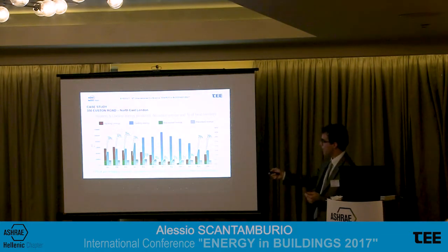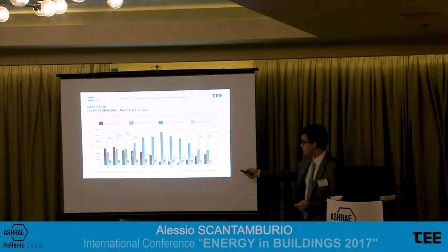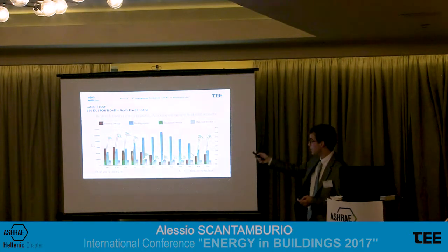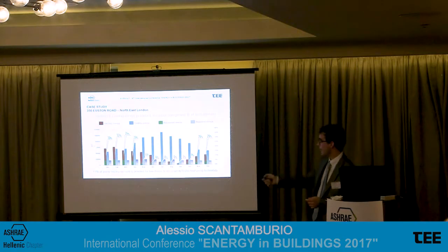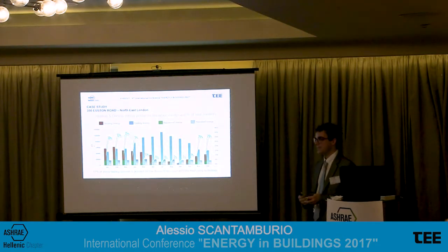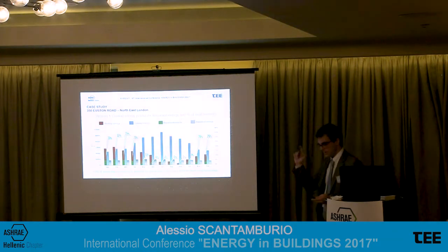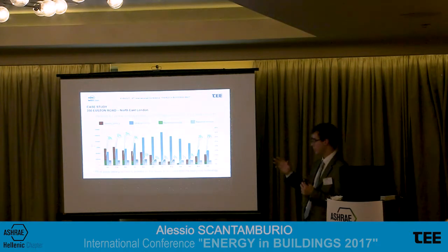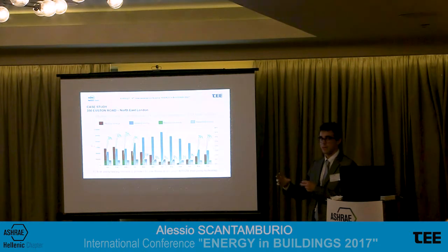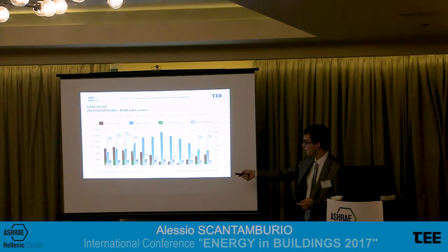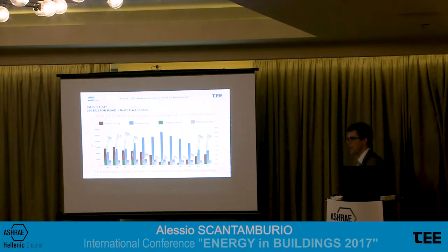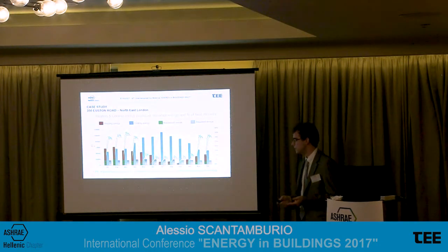So, as you can see, it is true that this plant is requiring heating and cooling for most part of the year. As you can see, the blue line and the red line are cooling and heating demand. The gray line is the power, the energy consumption of the unit, and the green line is the energy which is recovered, let's say, for free. In the previous slides, we saw that when the 4-pipe system is producing hot water and cold water at the same time, we can consider that one of these useful effects is for free. And this is the meaning of this green line. So, this is from the numbers in terms of power, cooling, heating, recovered energy.